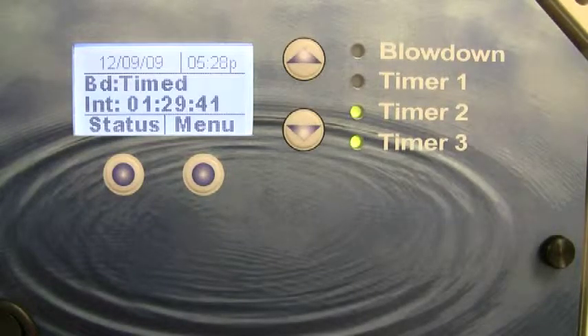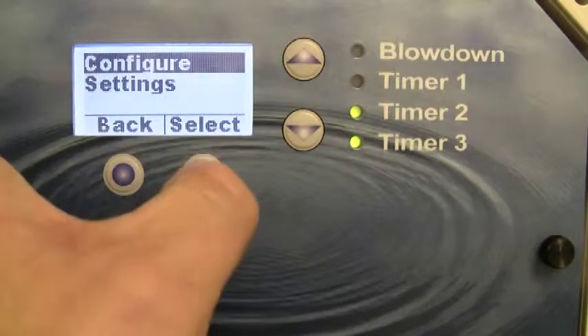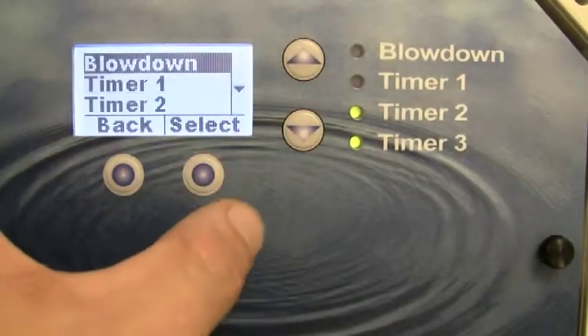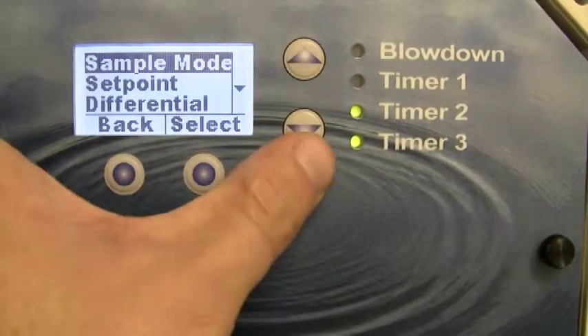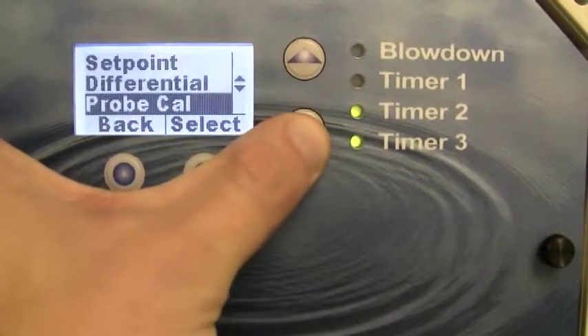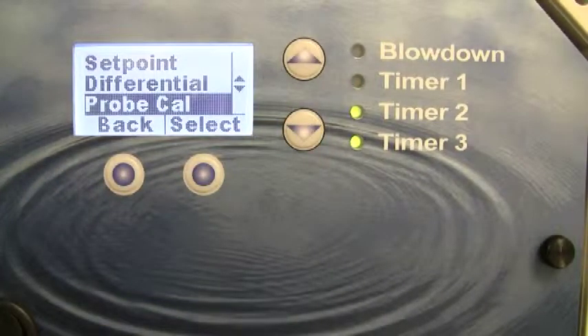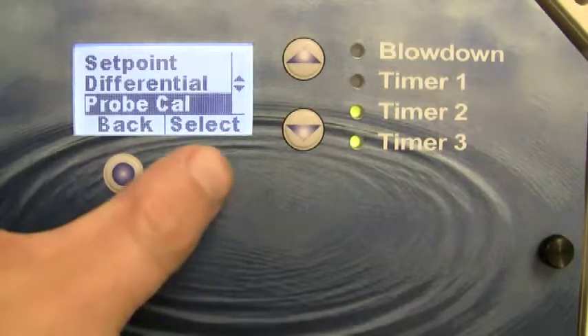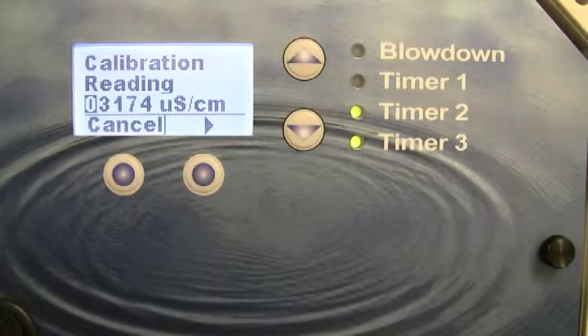Calibration is simple and intuitive. Simply press the menu button, enter the settings menu, then the blowdown menu, and arrow down to probe cal. When you press select, the controller will prompt you to enter a value that you can obtain with your handheld tester. This is the actual conductivity of the boiler.